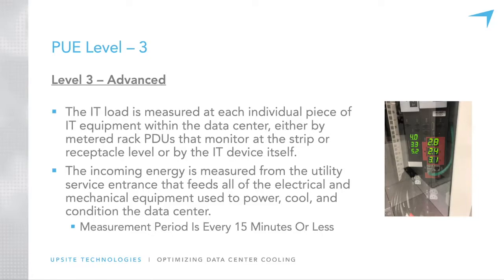So I know when I first started looking at PUE and the measurements of PUE, why does it matter to me, minute to minute, 5-minute segments, 10-minute segments? Even from the PUE level 1 measurement to if you were using PUE level 2, you could see a little variance in what your PUE is just based on the measurements, the power factors that are associated with the UPS system. But also, as your CPU utilization ramps up and down based on the number of users or traffic that you have in your data center, that's going to affect it. And also your outside temperature, outside humidity will have a great effect on there also.